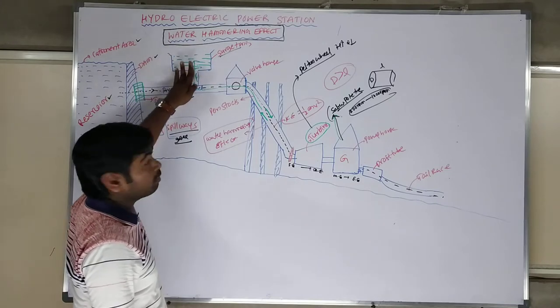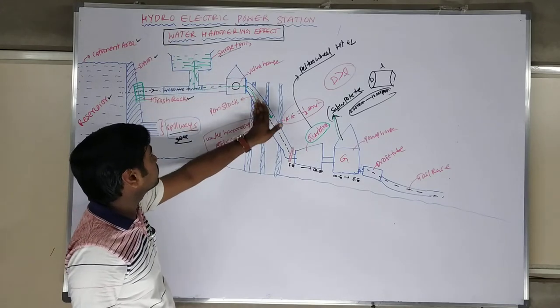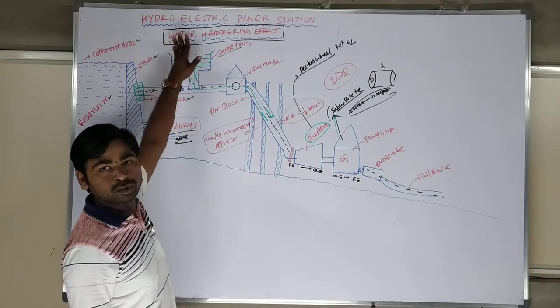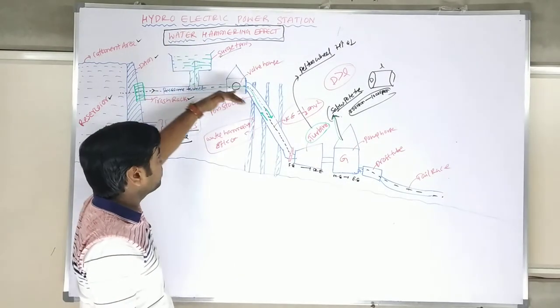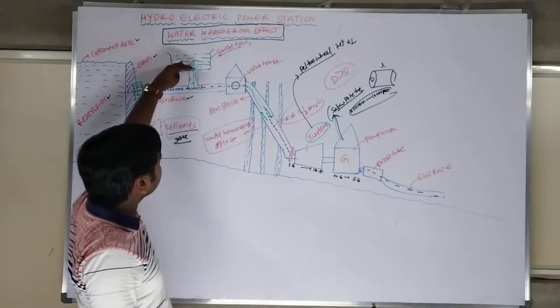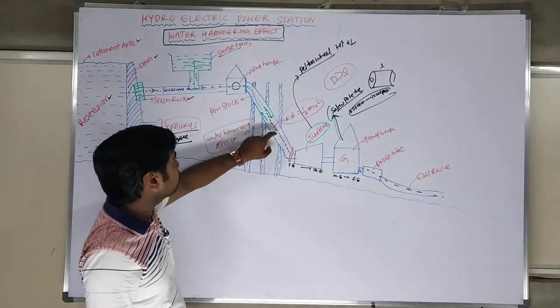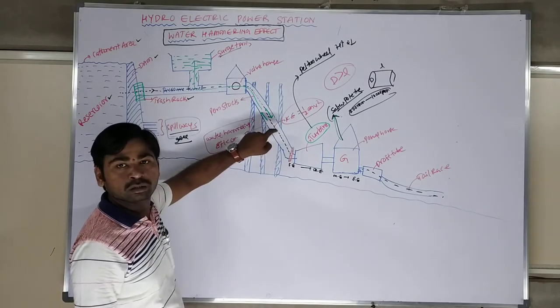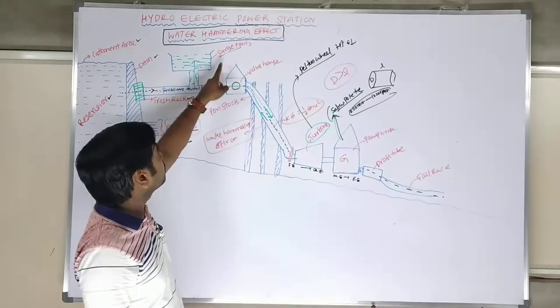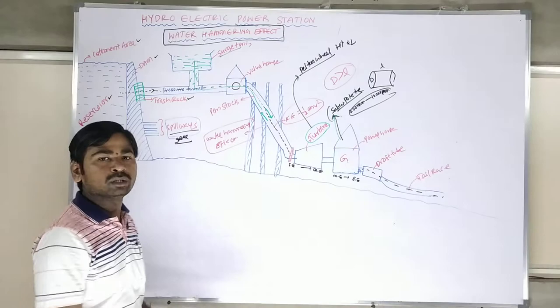The surge tank is a bypass mode. When high pressure occurs, water will go up and be stored temporarily. When the pressure decreases, the water level will go down, go back to the penstock. Therefore, this water hammer effect which will be developed in the penstock will be protected by the surge tank.